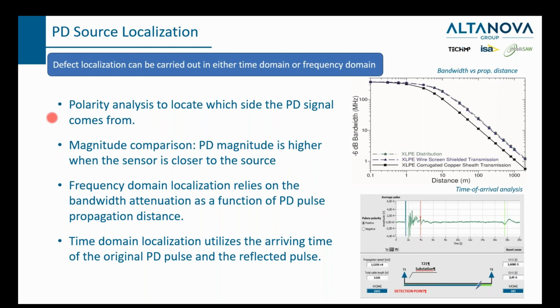A very simple method is to use polarity analysis to locate where the discharge comes from. For example, if we have a sensor installed in the middle of a cable, for example on a cable splice, the measured PD pulse, the current pulse, has a direction, right? So we can use the polarity of the pulse to tell if the signal is coming from the left part or from the right part. The same thing happens if we have the sensor installed at the cable termination. If the signal comes from the part above the termination, it will have positive polarity. If the signal comes from the equipment below the termination, like the cables or splices, it will have negative polarity. So that's a simple judgment rule to locate roughly where the signal comes from.